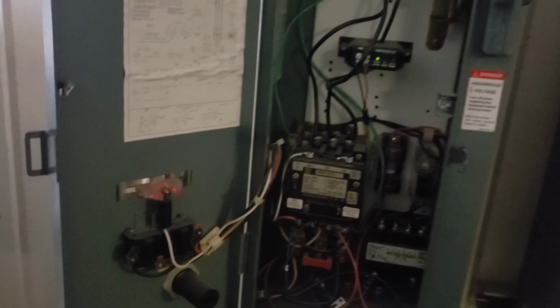And then this last one I'm on, got here and one of the control fuses was blown. I went through, checked the system, didn't see anything immediately a problem. I didn't find any immediate shorts or anything else, so I'm going to replace the fuses. Had to go pick some up, and we're going to re-enable this thing. Let's see if we can. Look at there, works like a charm.